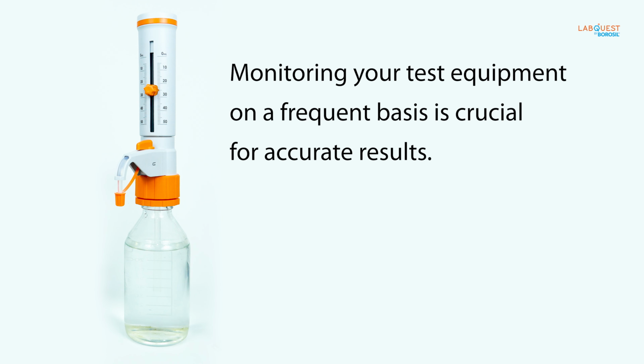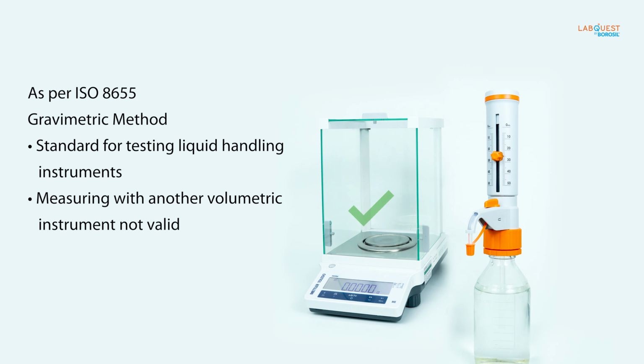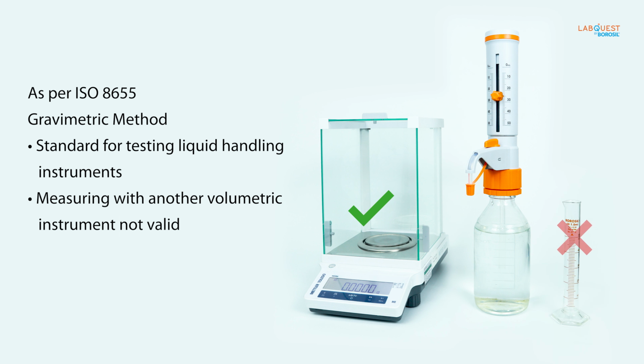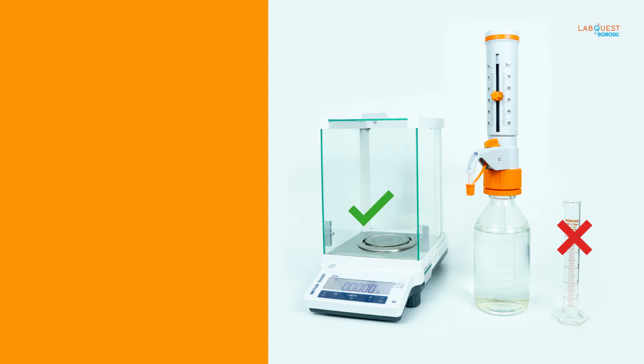Monitoring your test equipment on a frequent basis is crucial for accurate results. In accordance with ISO 8655, the internationally recognized standard for assessing piston-operated liquid handling instruments, the recommended calibration method involves gravimetry. It's essential to perform precise testing and calibration for liquid handling devices, and it's not advisable to rely on alternative methods, such as using a graduated cylinder to evaluate a dispenser's performance.